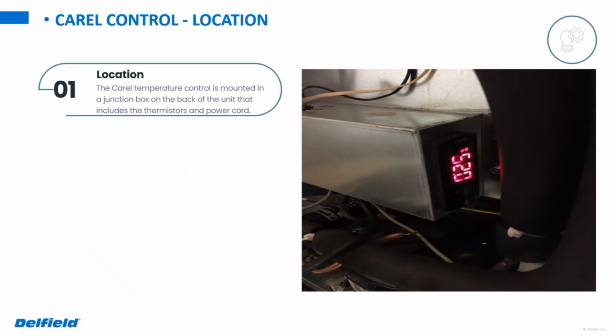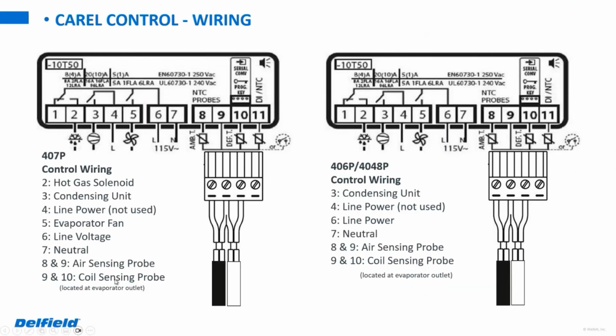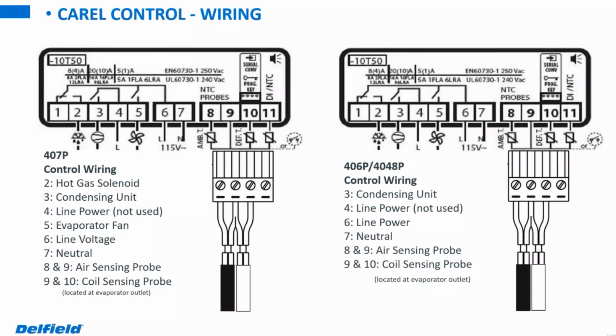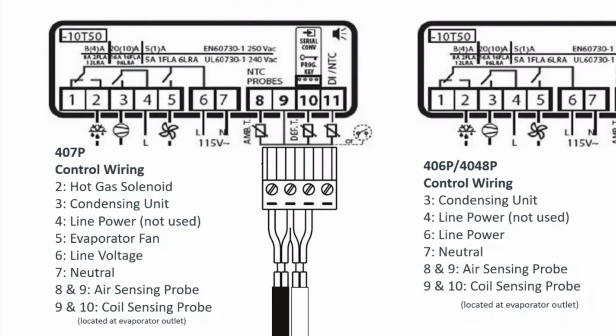As far as the location of the control, it's always going to be located on the back of the unit, normally in a metal junction box. Control will be mounted sideways in there with the probes plugged into it and all the electrical connections coming in. As far as the wiring goes, we'll start out with the 407 there on the left-hand side. You'll notice that we have a hot gas solenoid that's going to be for defrost on that. So these ones do not have an electric heat on them. Those ones will just have the hot gas bypass on there.